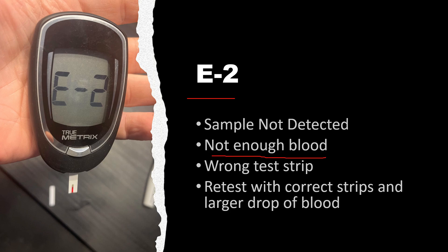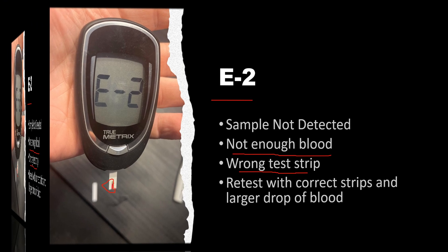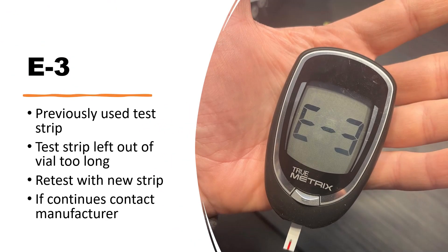E2 means a sample was not detected — simply that there was not enough blood. Typically the blood will go all the way up the test strip, so ensure that you have an appropriate size drop of blood. It could also mean that you are using the incorrect test strip for this meter.